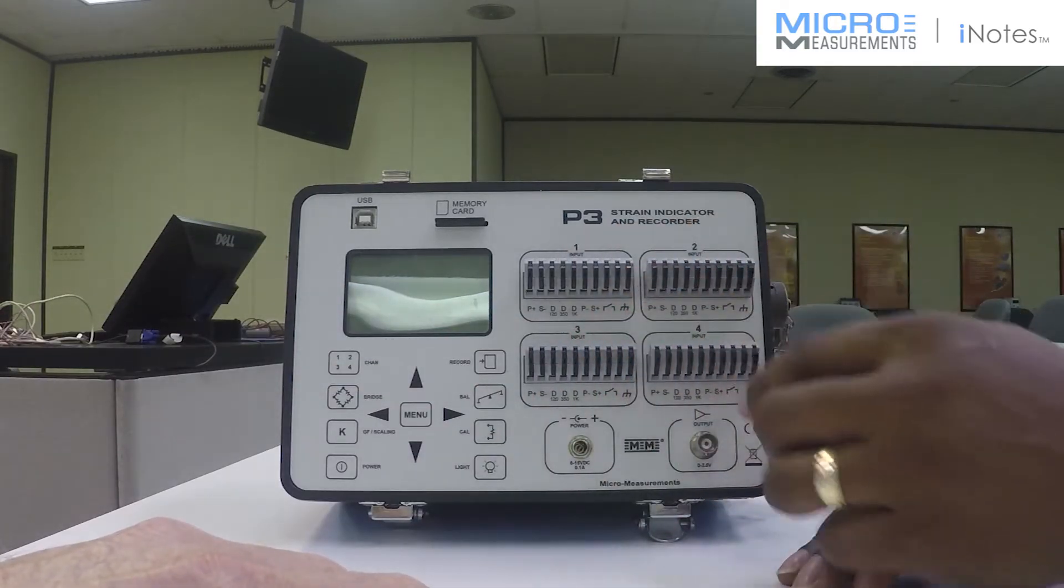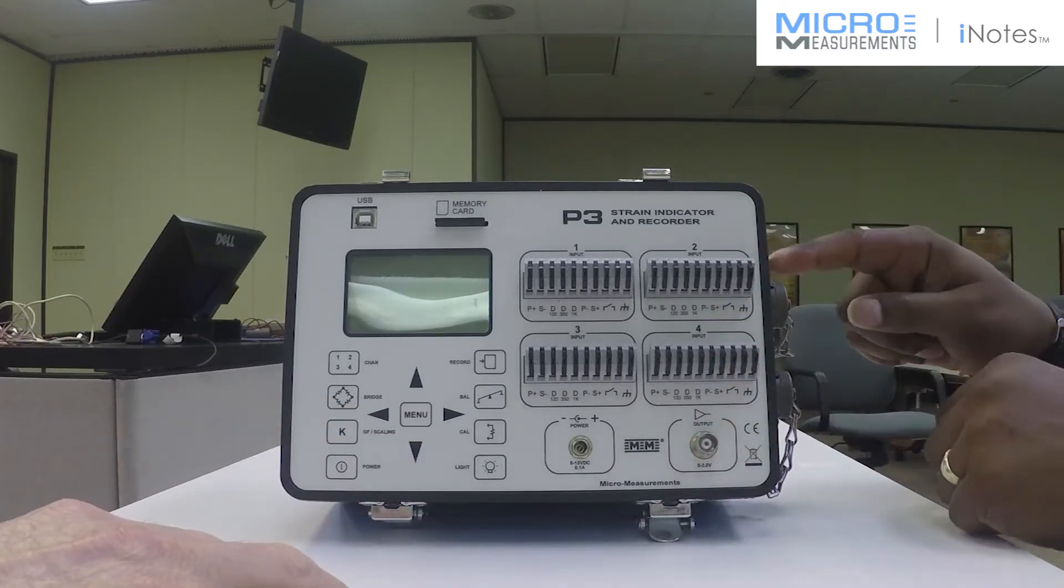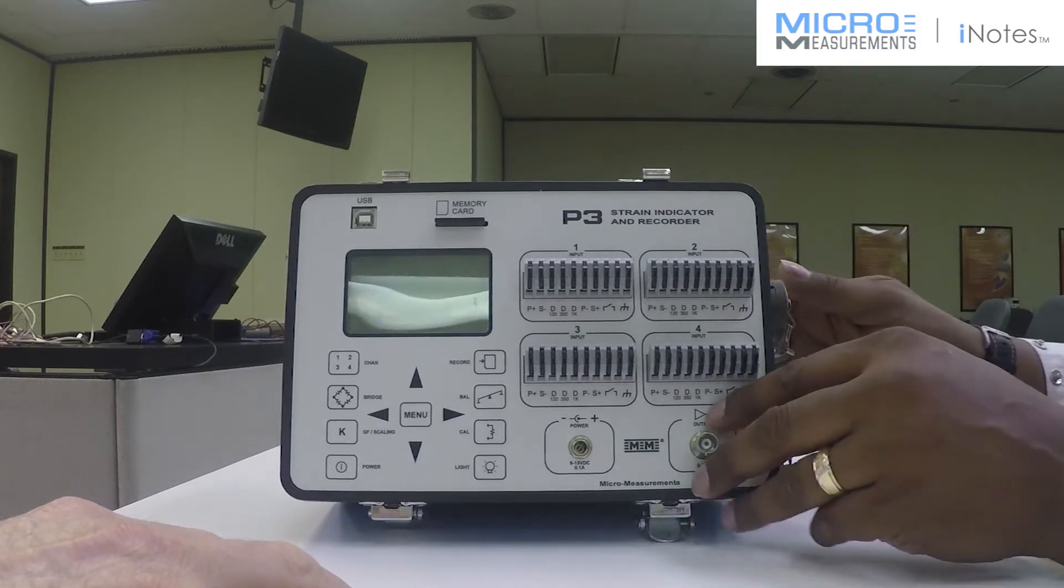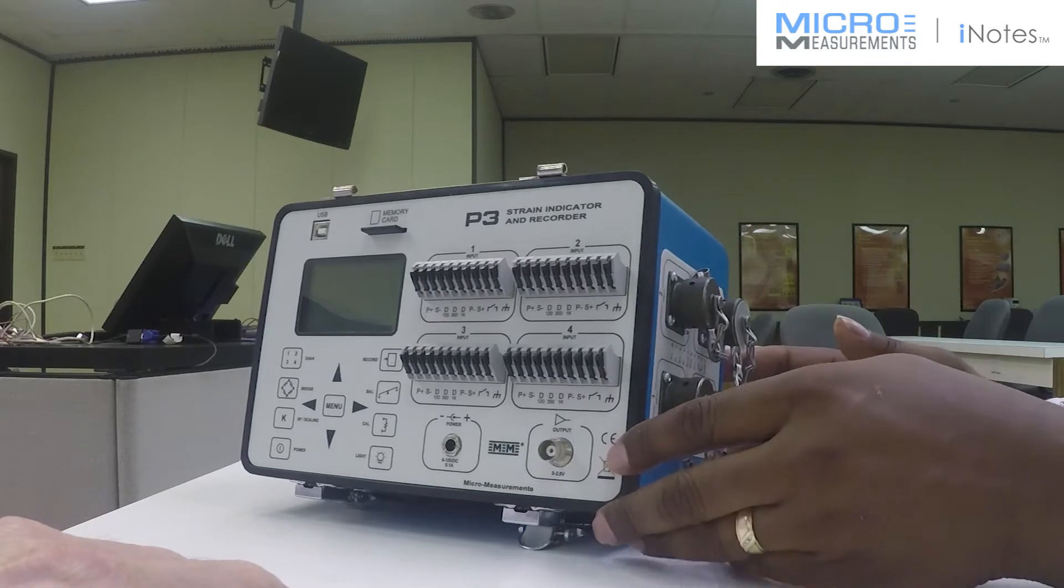Can you connect up transducers to this? Yes, you can. You can either use the standard connection if the transducers are wire-based, but if they have some type of Bendix connector or twist-lock connector, there are connections on the side of the unit here that will allow you to connect your transducers as well. I see, very good.